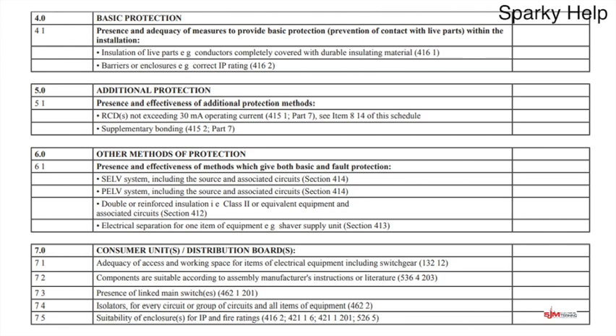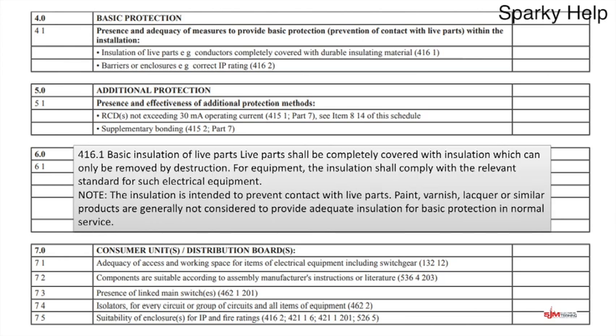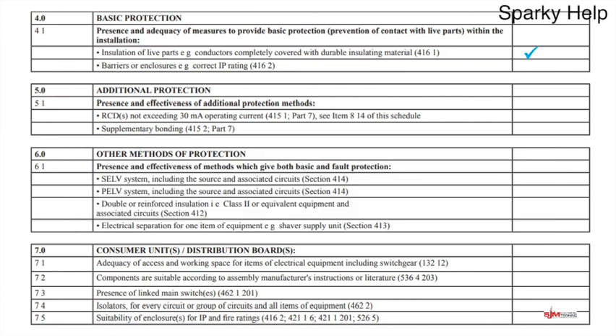Barriers and enclosures is about IP ratings. So here we've got the insulation. This is all the regulation. It says basic insulation of live parts shall be completely covered with insulation which can only be removed by destruction. Bear in mind, most of the time the manufacturers put this on for us, so we don't have to worry about it. There's a note, not that anyone would, I wouldn't have thought: for live parts you can't use paint, varnish or lacquer to insulate. Don't know why anyone would do that. So that's going to get a tick.